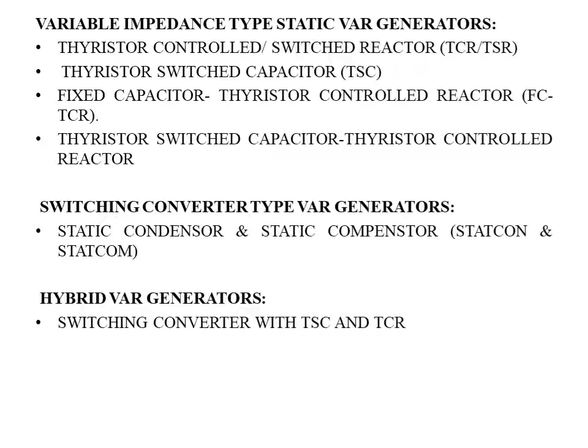So fixed capacitor thyristor controlled reactor. As I have discussed earlier, in case of static VAR compensator we can have control over the current injection by controlling the back to back connected thyristors by providing a gate signal or gate pulse. So a basic VAR generator arrangement using a fixed capacitor that is permanently connected with thyristor controlled reactor, FCTCR. The current in the reactor is varied by the method of firing delay angle control, that is nothing but by controlling the firing angle alpha, and this control signal is provided to the gate terminal of the thyristors.